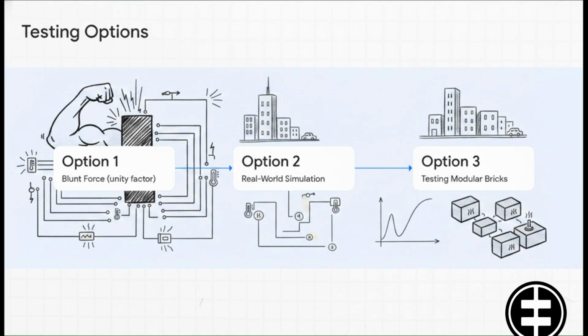Temperature rise verification is notoriously time-consuming, so manufacturers actually have 3 options to tackle it. Option 1 is basically the blunt force approach. Every single outgoing circuit is loaded to its maximum rated current at the exact same time. That's a unity diversity factor. It's an incredibly onerous test, pushing the system way harder than most real-world applications ever will. Option 2 is a real-world simulation where circuits are loaded based on a rated diversity factor, which is a lot closer to normal loading conditions. And finally, Option 3, well, it's kind of like testing Lego bricks. For flexible, modular systems, the horizontal bus bars, vertical bus bars, and individual units are tested separately first, and then the whole assembly is verified. This totally avoids having to test every single possible custom arrangement.